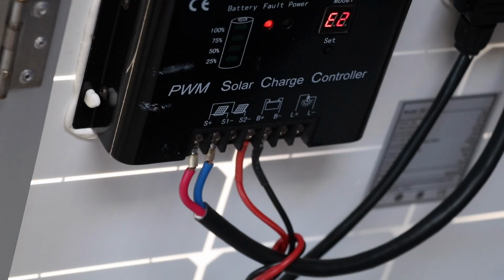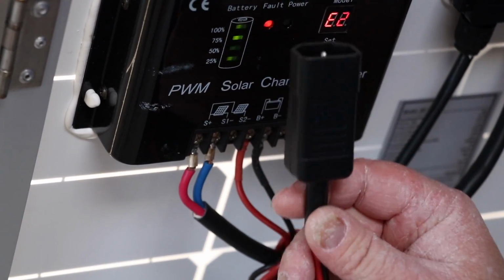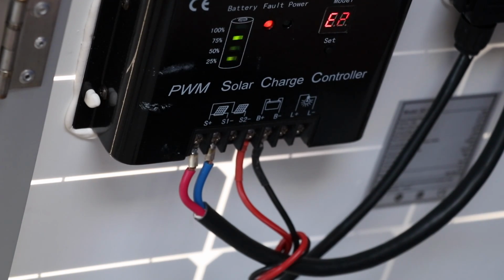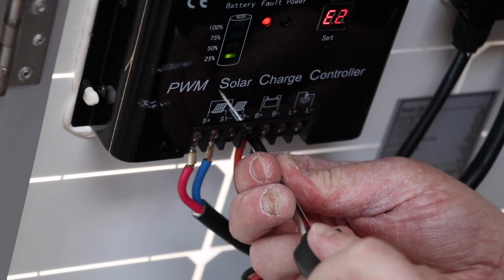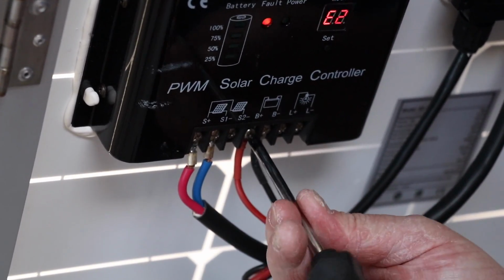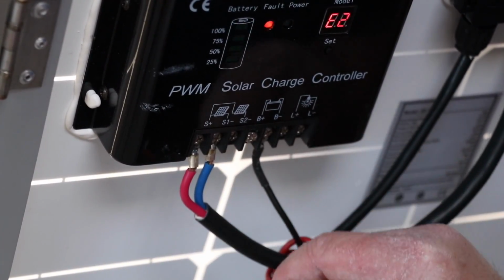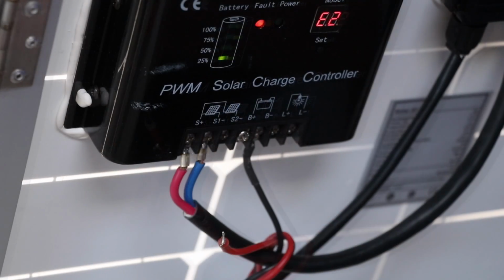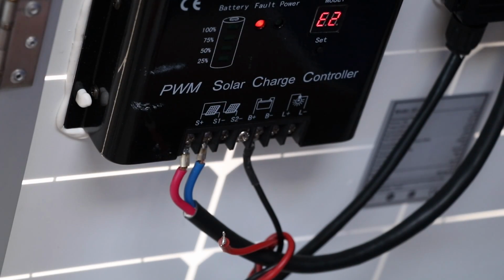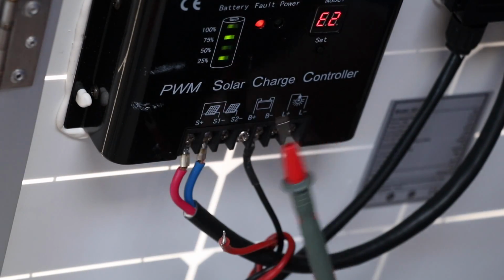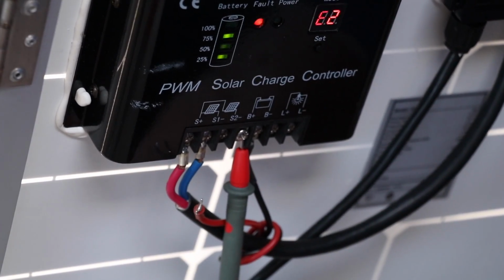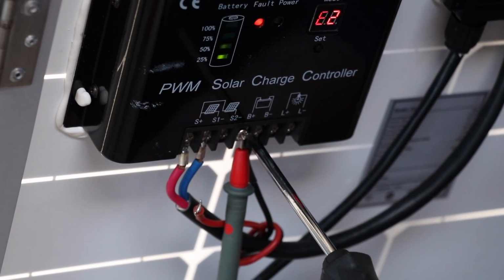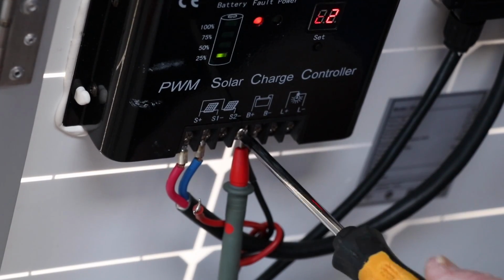You can probably still see error messages here, because we're still disconnected from our battery. So I'm going to disconnect the terminal that normally goes to the battery, just pull that out. Another thing I'll do to make life simpler is stick my positive probe into the screw terminal and tighten it up - you'll see why in a moment.